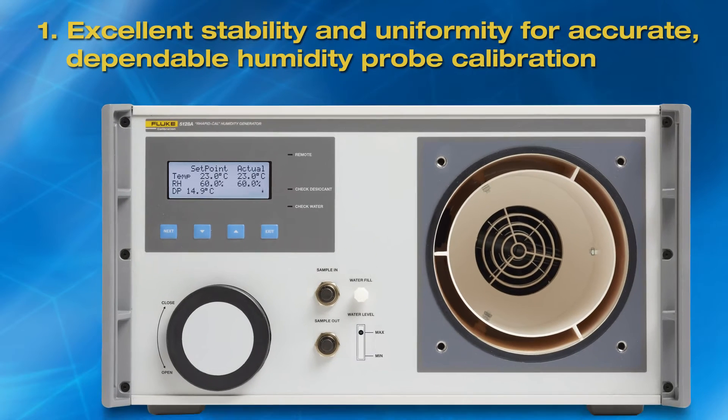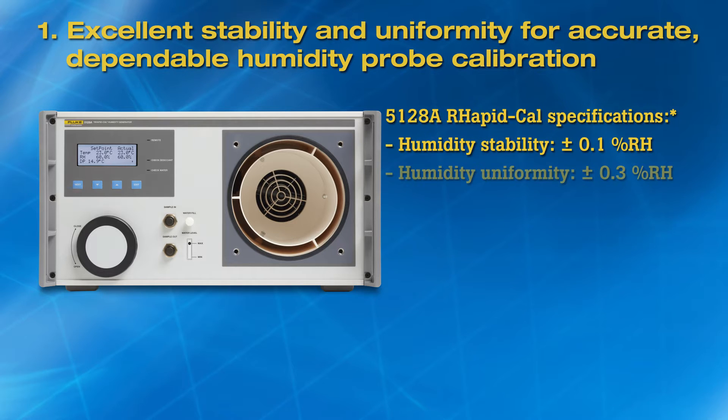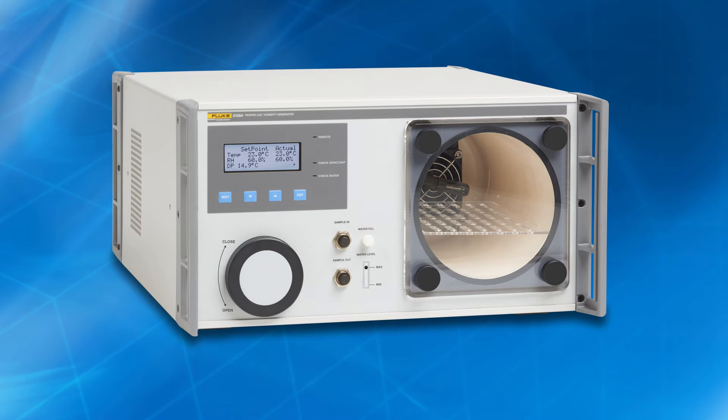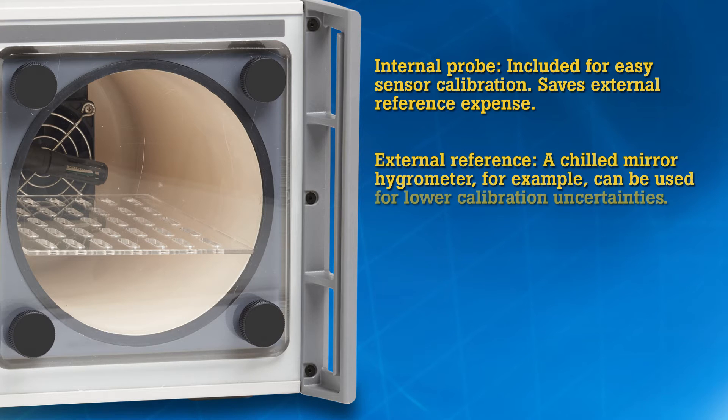First, excellent stability and uniformity. Chamber stability and uniformity are two important specifications that impact accurate, dependable humidity probe calibration. The 5128A RHapid-Cal offers excellent stability and uniformity for a portable humidity generator. Some competing generators don't even specify any measure of uniformity. The 5128A RHapid-Cal incorporates an internal probe for easy sensor calibration and to save the expense of an external reference, but an external reference such as a chilled mirror hygrometer can also be used to obtain lower calibration uncertainties.